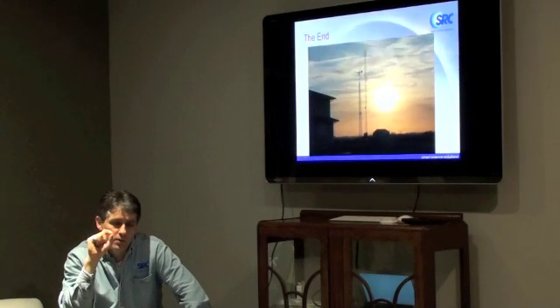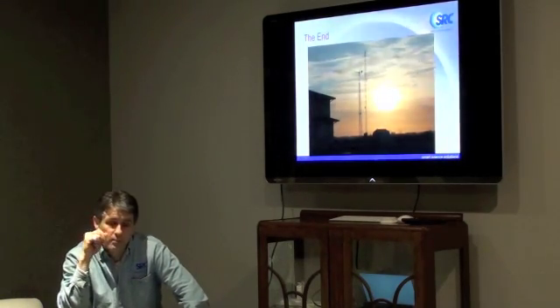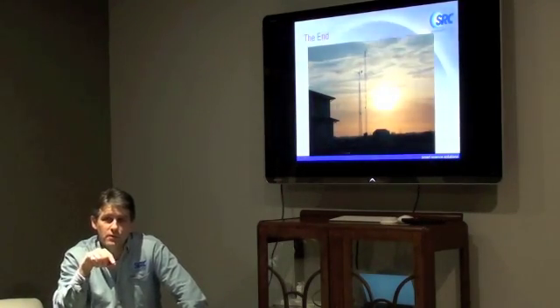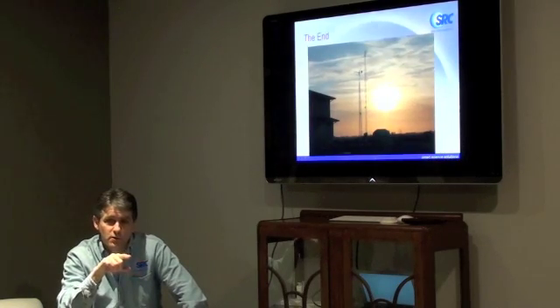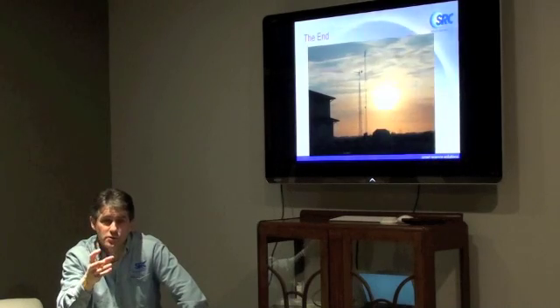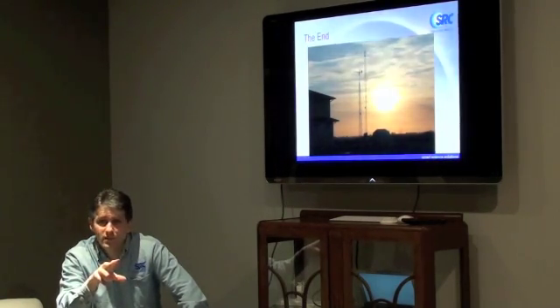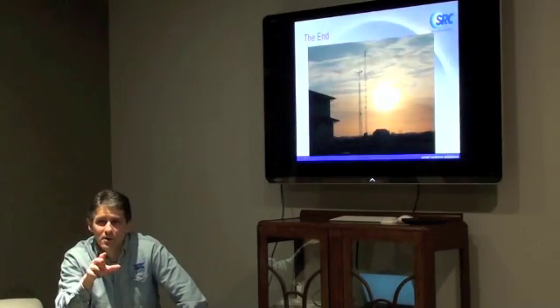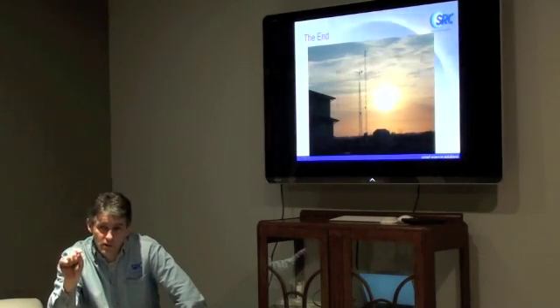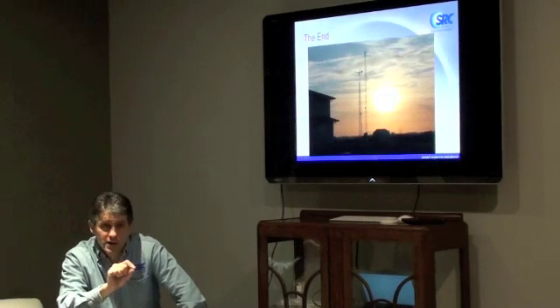Now there's an interesting sort of philosophy thing here when it comes to solar thermal. The guy who was told to install the meters was told to monitor the solar collector output. Basically, the amount of heat that's captured. Turns out that's a useless piece of information. It's just irrelevant. Because what you really want to know is how much solar thermal energy you are pulling out of the solar thermal storage tank and putting into the house. That's the number that matters.